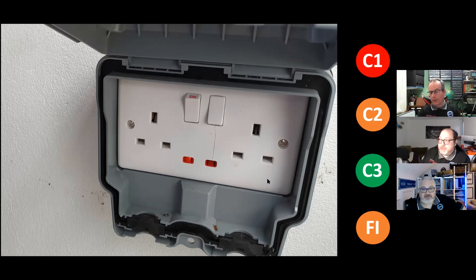Can I see to it just for the neons? Because the neons were a great idea years ago, so that people could have a visual confirmation that the power supply to that equipment was live. But they're a nightmare when doing testing, and they always fail anyway, and then they just make the accessory look rubbish. So it's a C3, but I'd probably see to it now because it's BG and neons. And the neons are pointless because when the cover's closed, you can't see them anyway.